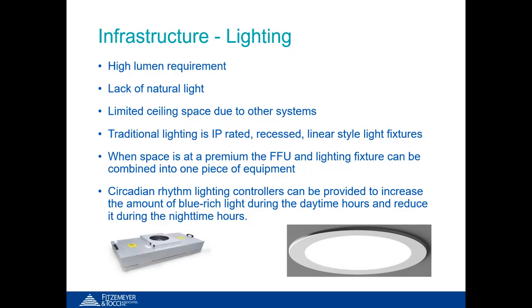Further studies, however, found that this blue-rich light is detrimental to night shift workers as it interferes with their natural circadian rhythm. Most pharmacies typically operate 24/7 along with the rest of the hospital, so it's important to factor in the effects these light fixtures will have on the health of both day and night shift employees. In order to minimize the negative health effects of the lighting, circadian rhythm lighting controllers can be provided to increase the amount of blue-rich light during the daytime hours and reduce it again during the nighttime hours.